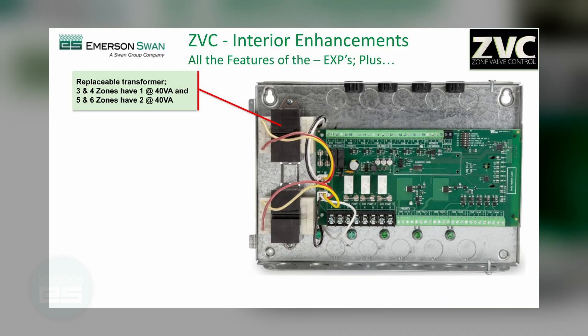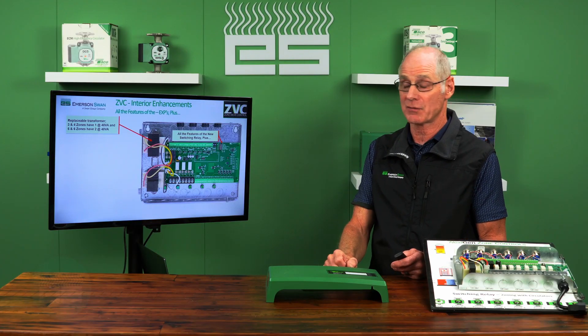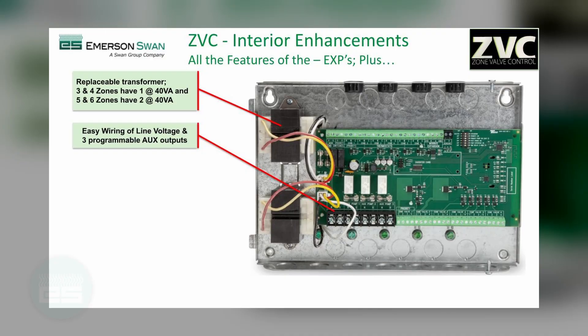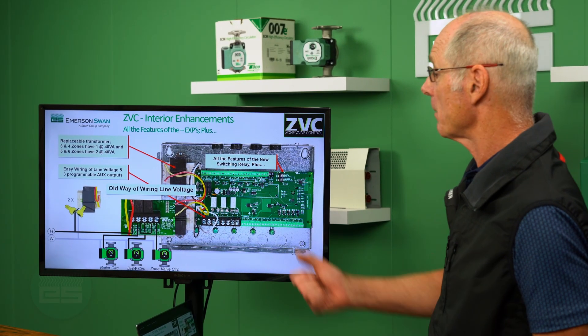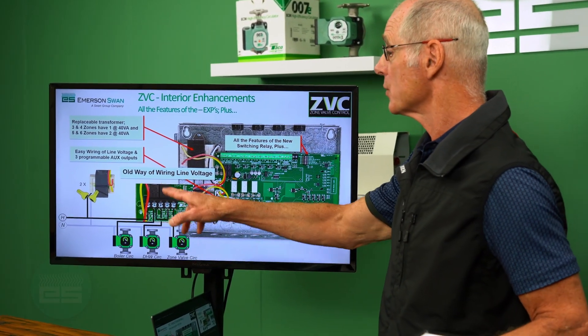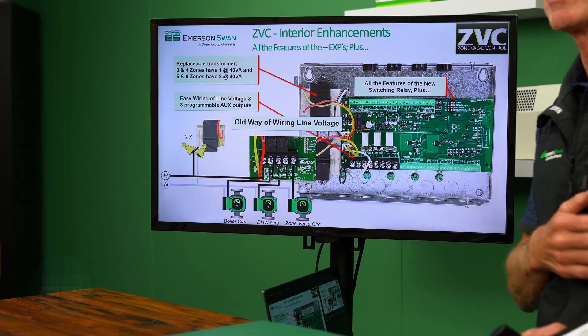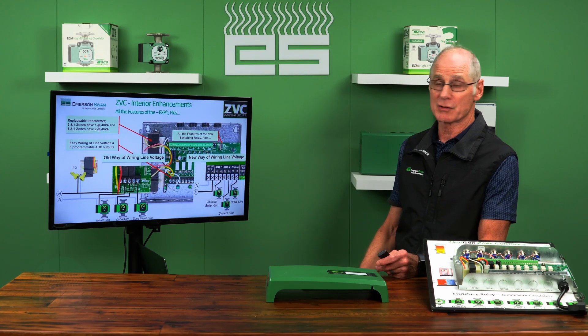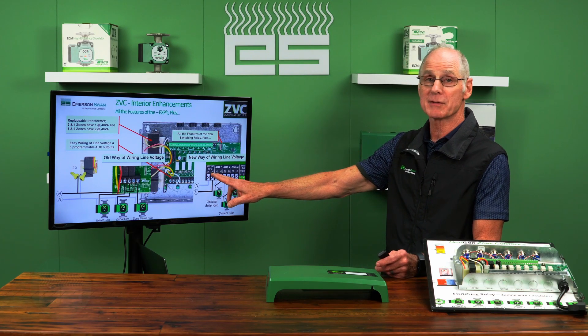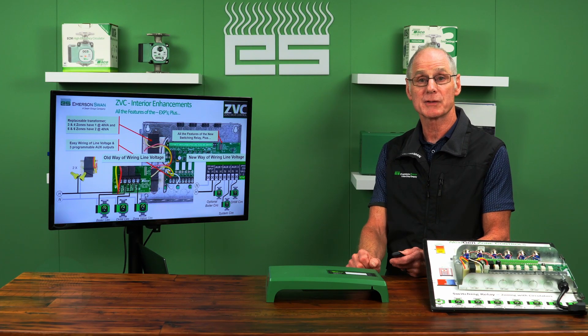On the three- and four-zone models you have a 40VA transformer, and on the five- and six-zone models you have two 40VA transformers. The old way of wiring the line voltage was slightly cumbersome. For example, if I had three pumps into an older model, I had to bring power in, do jumpers, run each one, and then bring power to the transformer. On the new version, it's so much easier — you just bring power in to the hot and neutral and you have three line voltage outputs ready to go.